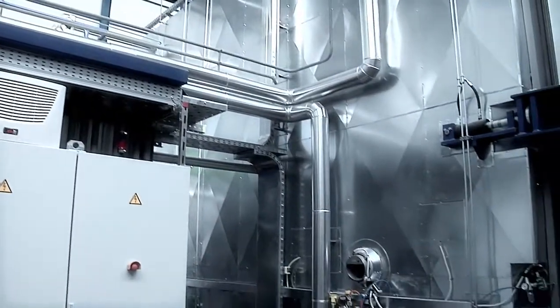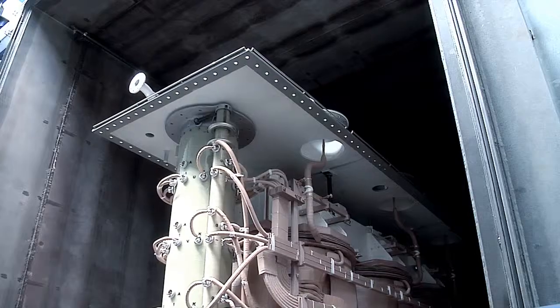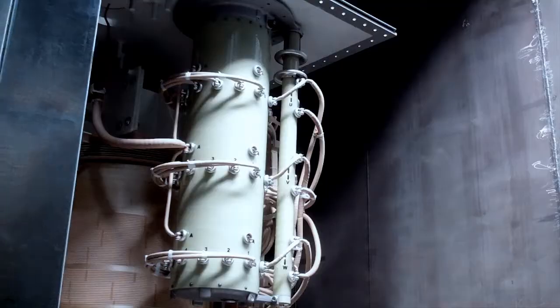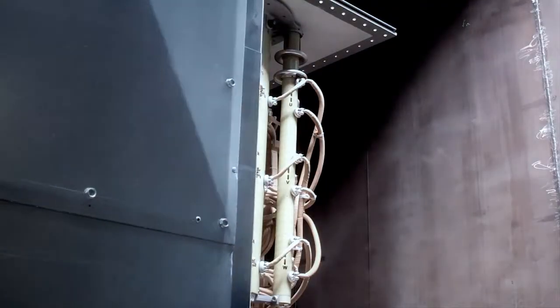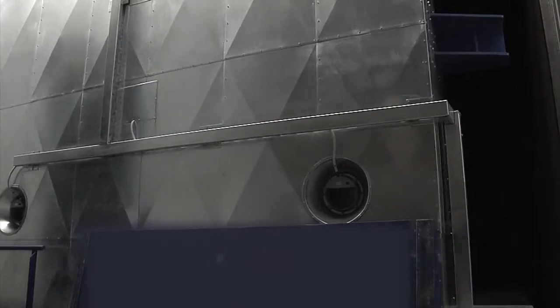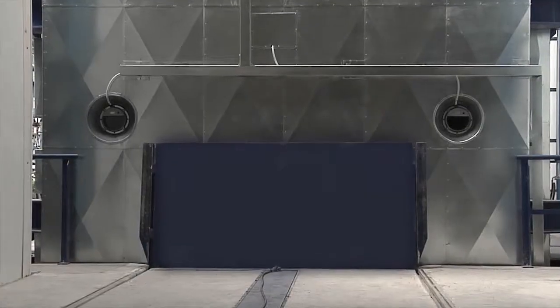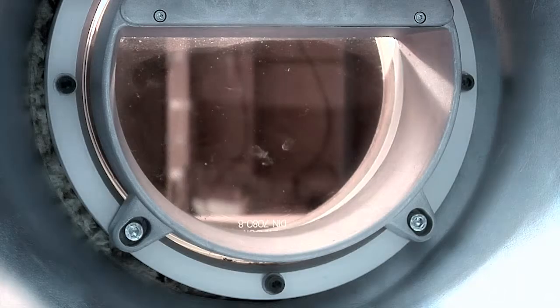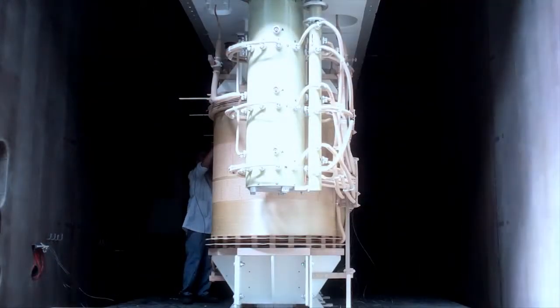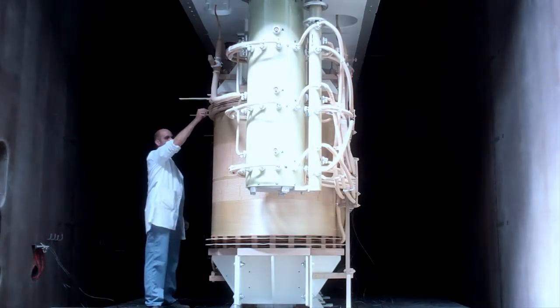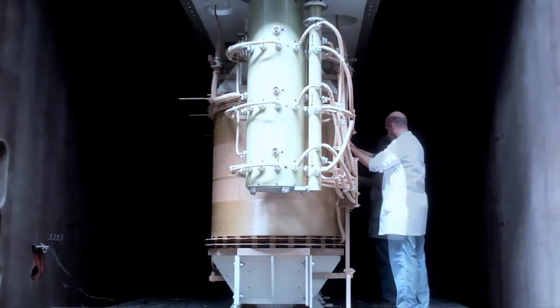This system is based on impregnating the active part of the transformer with kerosene under vacuum. This component is highly hygroscopic, enabling residual humidity to be extracted in a totally efficient way, especially from the cellulosic components of the machine, carrying out a drying process more effective than traditional hot air convection methods.